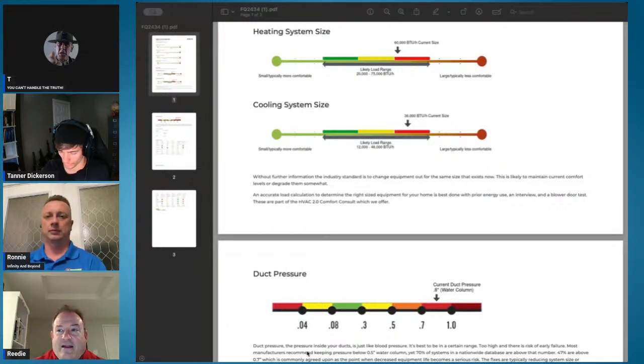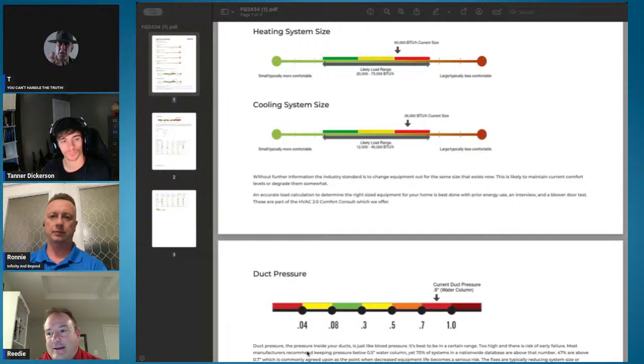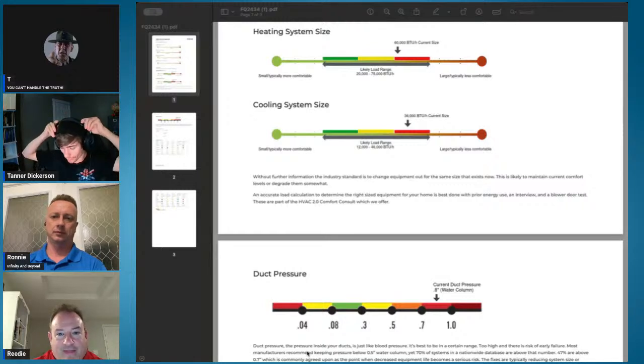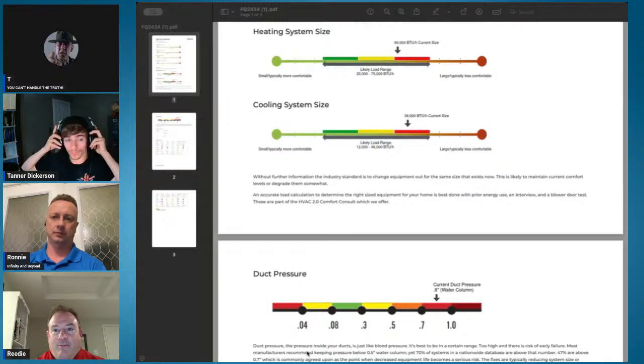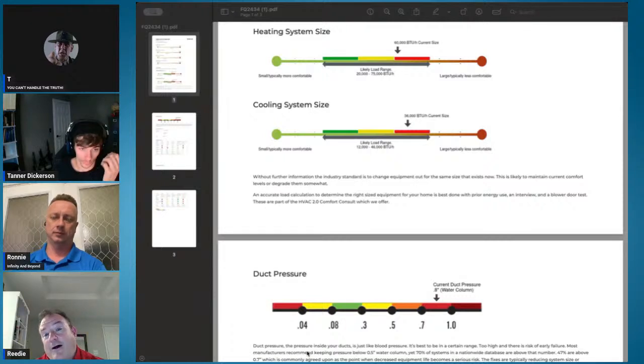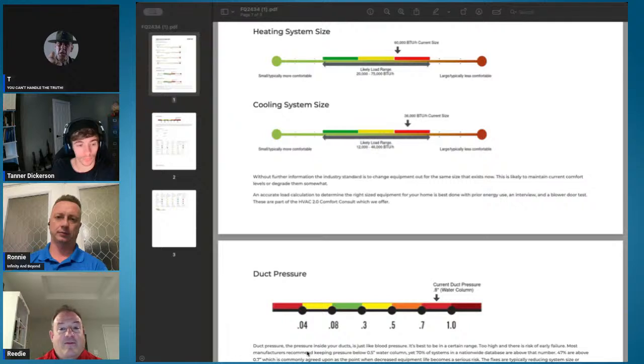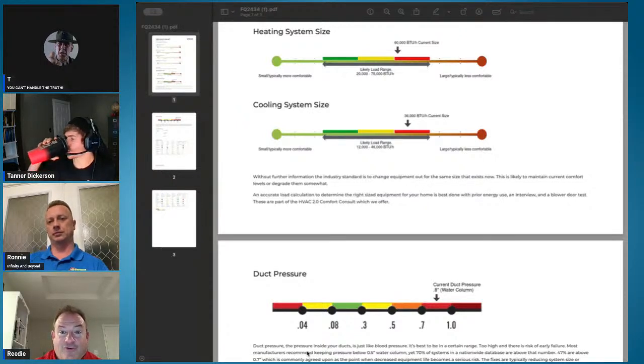In effect, I did the Manual J like you're supposed to, no blower door or anything like that, and we came up saying 31,000. If we'd put a blower door in that, it probably would have been lower. He's got a conditioned basement, and very little of that house is crawl space. Who knows what the attic leakage was going to look like, but the reality is 3 tons has worked just fine for him.